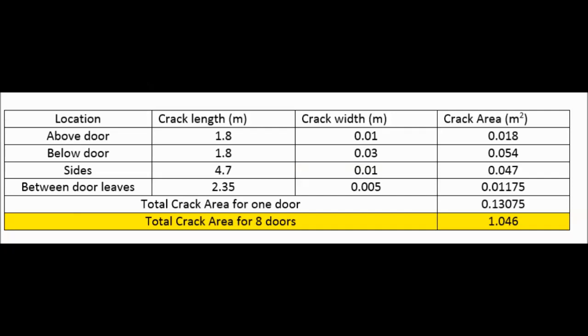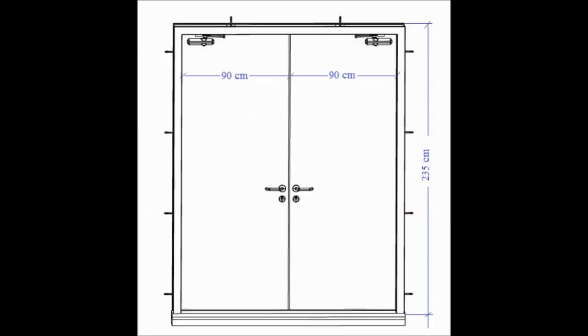The building is utilizing 8 doors with the presence of a buffer zone, or entrance lobby. This limits infiltration to be only due to the cracks around the doors, without considering any open door at any time of operation. This is a typical door of the mosque. The door leaves are 90 cm width and 235 cm height. The crack from the sides and above the doors was measured to be less than 10 mm, while the crack between the leaves was measured to be less than 5 mm. The crack at the bottom of the door was measured to be less than 30 mm.